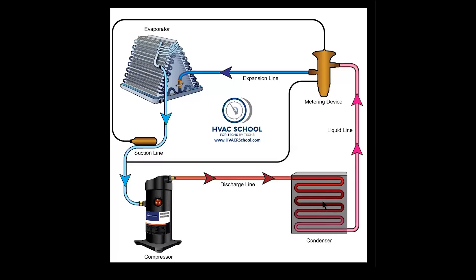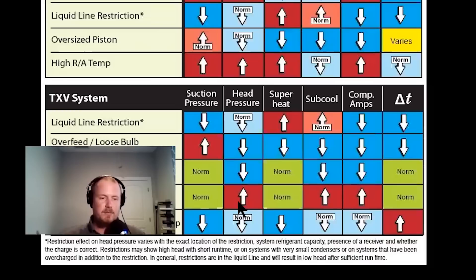We have to give a caveat: there are some condensers that are not designed to pump down. Today we have a lot of microchannel condensers, which have smaller internal volume and are not designed to hold the entire system charge. So make sure you don't pump down a microchannel condenser unless you know you should. Sometimes the charge can't be held in the condenser and is held in the receiver instead, and the location of the restriction can affect things.